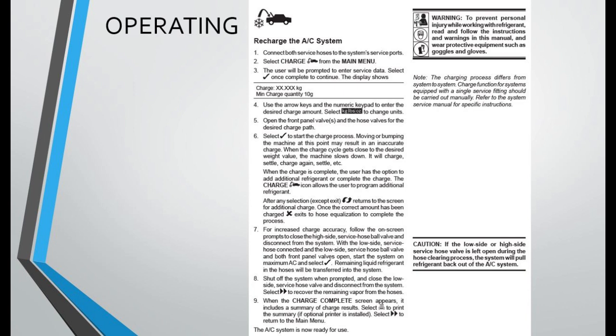7. For increased charge accuracy, follow the on-screen prompts to close the high side service hose ball valve and disconnect from the system. With the low side service hose connected and the low side service hose ball valve and both front panel valves open, start the system on maximum AC and select. Remaining liquid refrigerant in the hoses will be transferred into the system. 8. Shut off the system when prompted, close the low side service hose valve, and disconnect from the system. Select to recover the remaining vapor from the hoses.